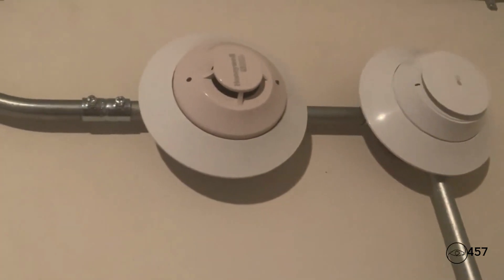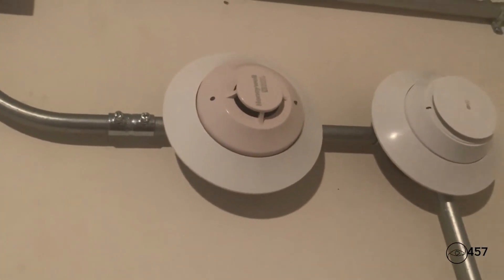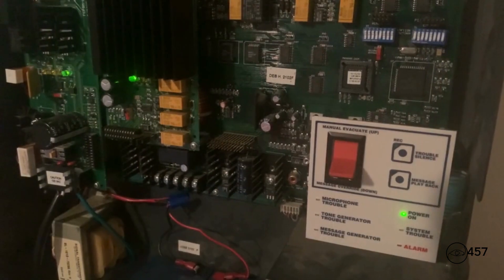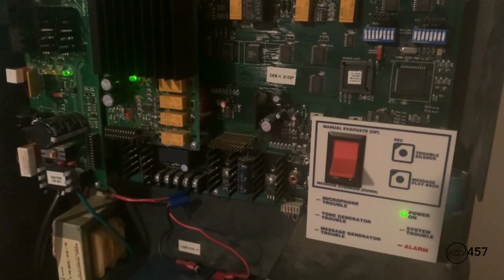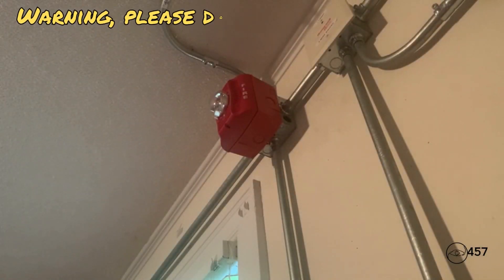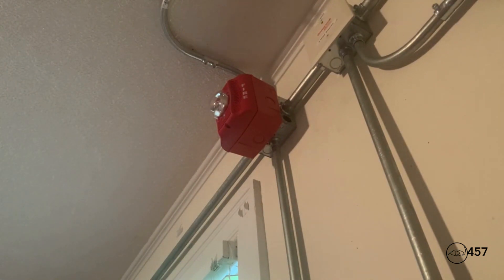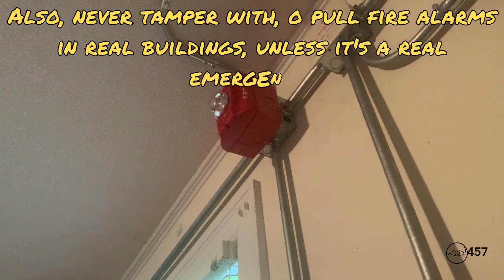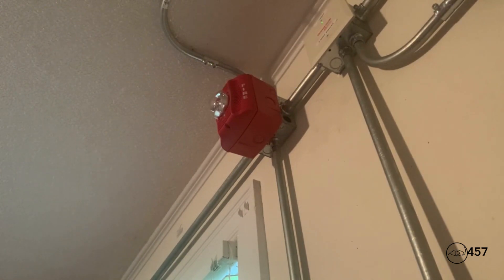We will be activating the SK photo with some smoke saber, and for our addressable pull station today we will be pulling the SK pull DA. For the VEC 2550 today I have it set on slow whoop and the voice message is enabled. Before we start, we are going to make one more announcement over the microphone: 'Attention in the building — we will be testing the life and safety system at this time. This is only a test. There is no need to evacuate. Please disregard all signals until further notice.